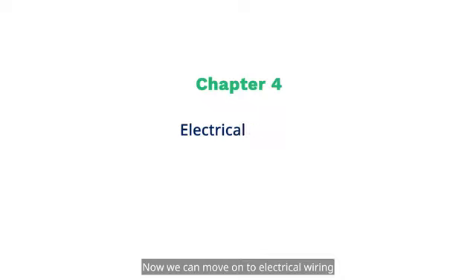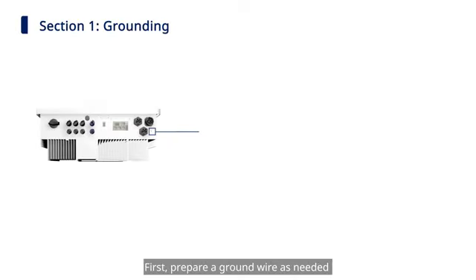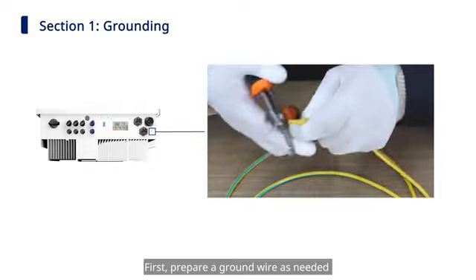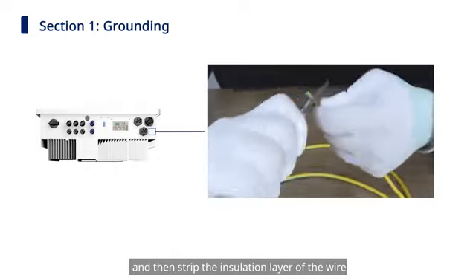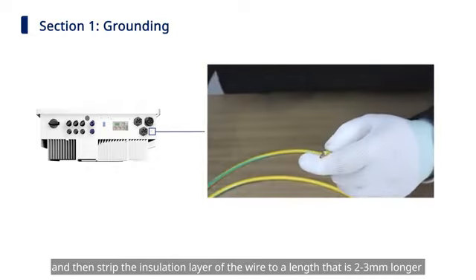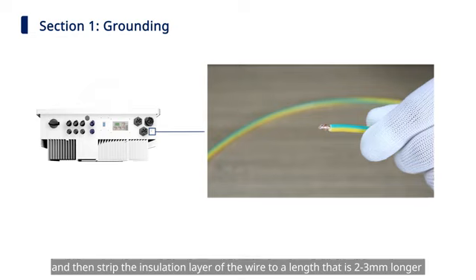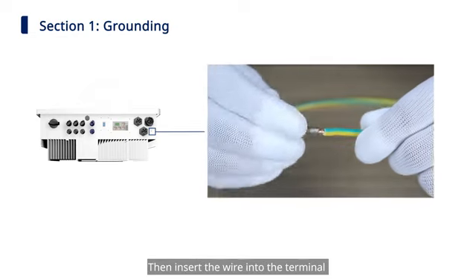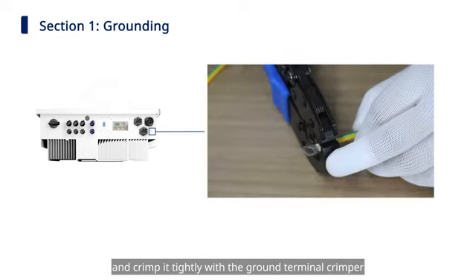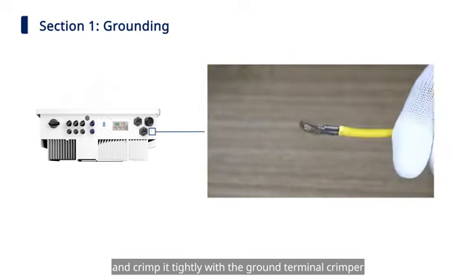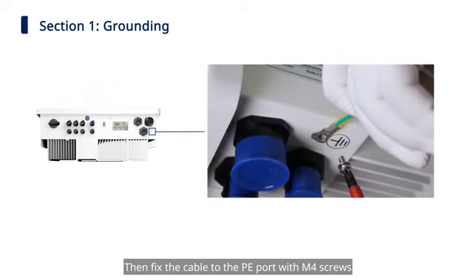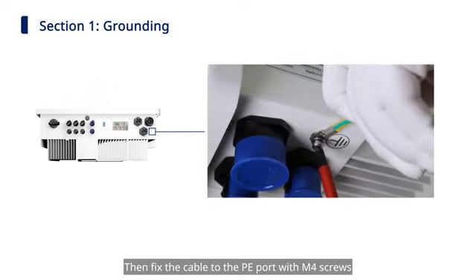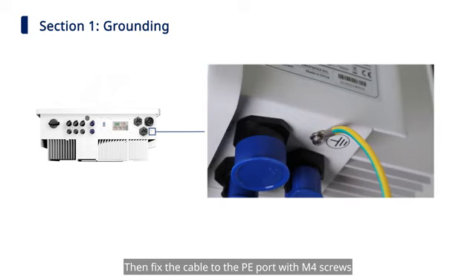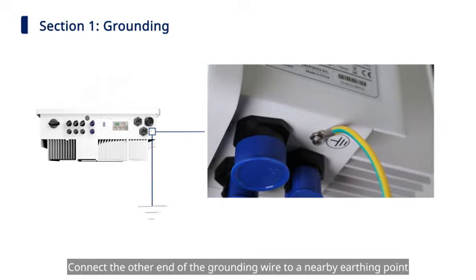Now, we can move on to electrical wiring. Section 1. Grounding. First, prepare a ground wire as needed, and then strip the insulation layer of the wire to a length that is 2 to 3 mm longer than the barrel of the terminal. Then insert the wire into the terminal and crimp it tightly with the ground terminal crimper. Then fix the cable to the PE port with M4 screws. Connect the other end of the grounding wire to a nearby earthing point.